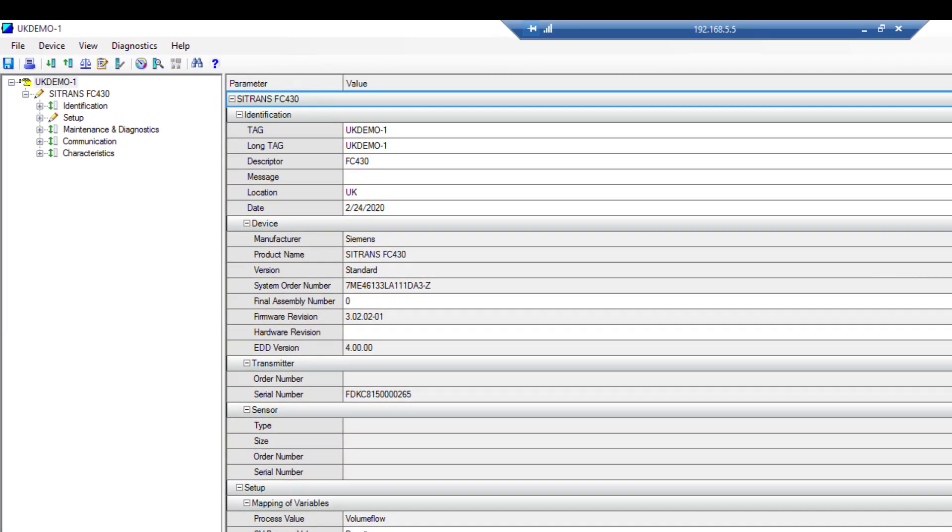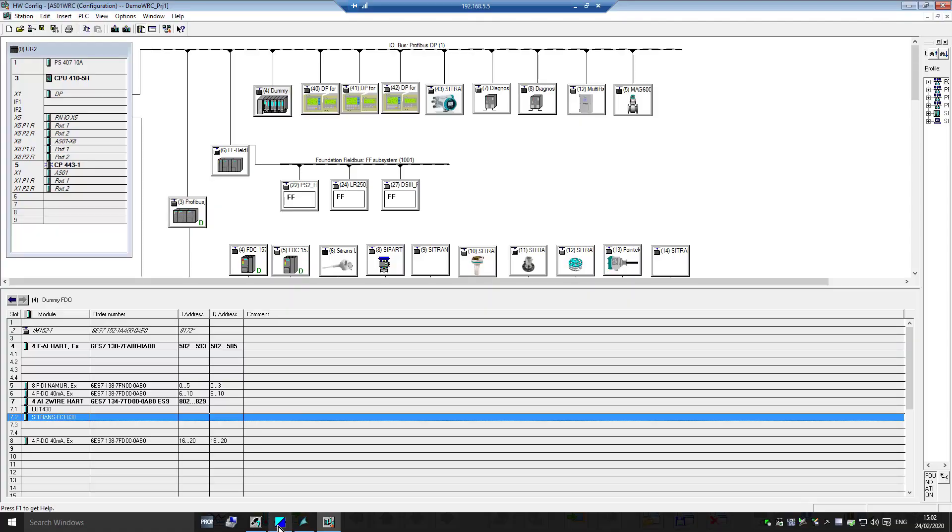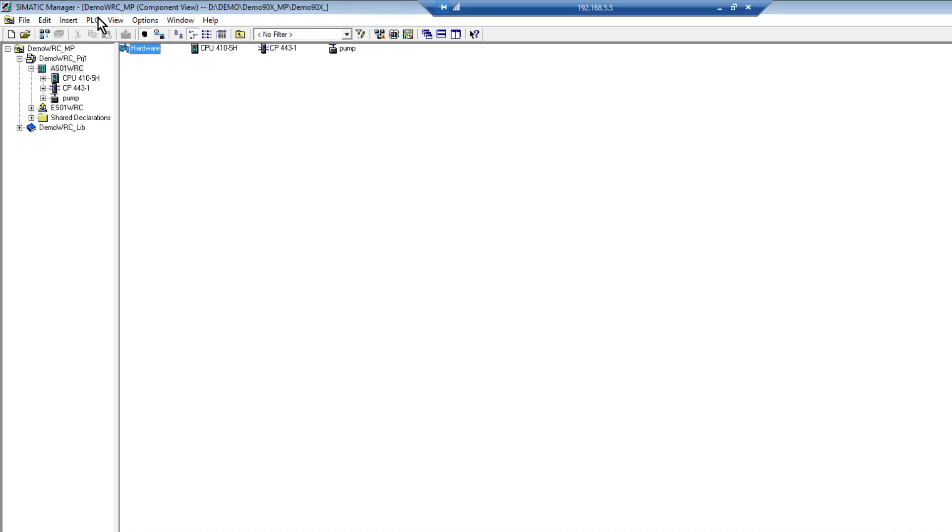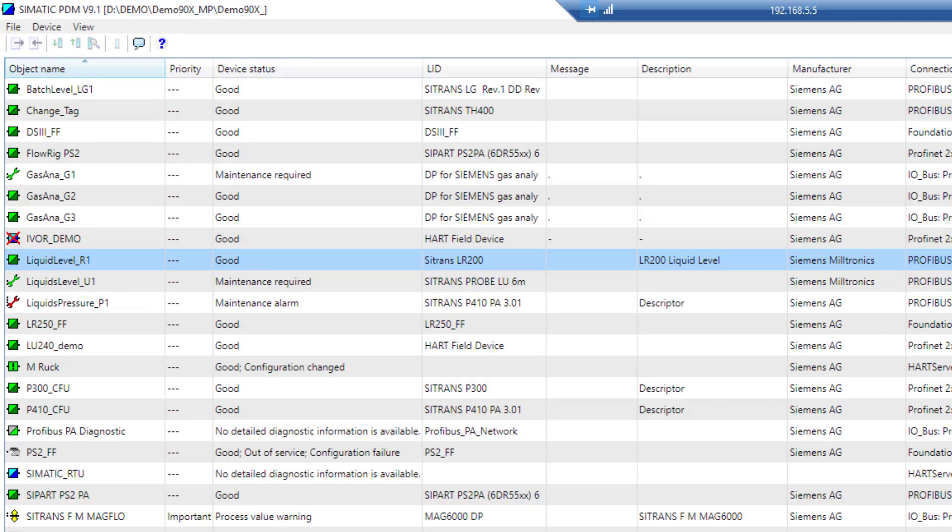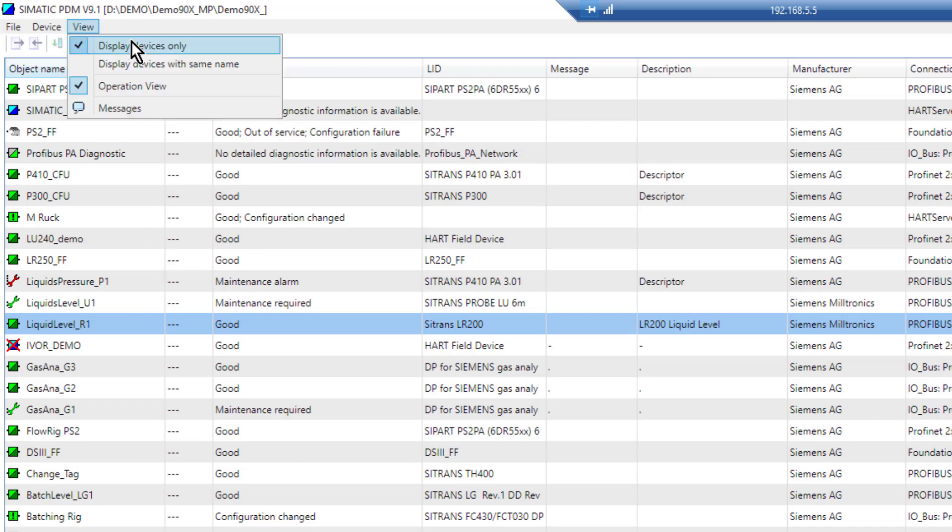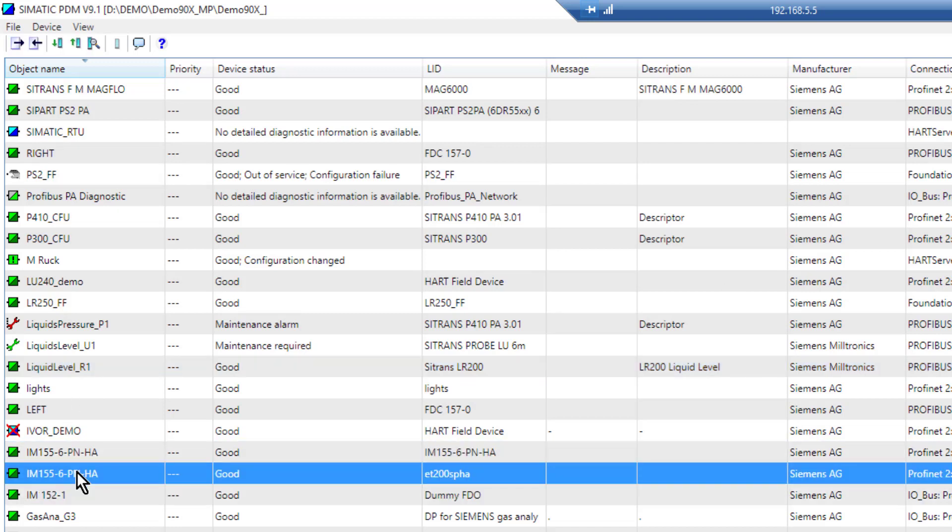I'm going to close that and save that. The last view I wanted to show you is within PDM—we have this device plant view. What's nice about this, if you have a lot of ET200 ISP or any HART remote I/O on site, it may be tricky to know exactly where each particular instrument is wired. When you come to use PDM, this view just lists all the devices via tag. So I can see alphabetically where my devices are. I can also—if I click on this, it's showing you the I/O, but I'm only interested in instruments. If you go view display devices only, I can see those are all there, and then I can go through and start working on each one of these.